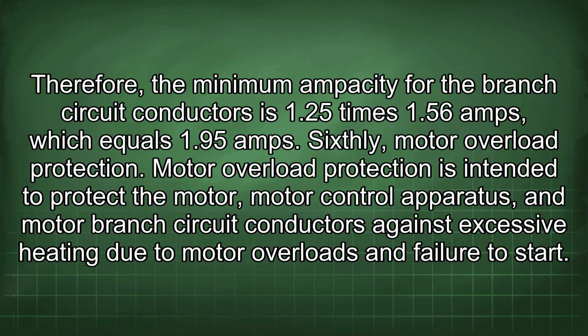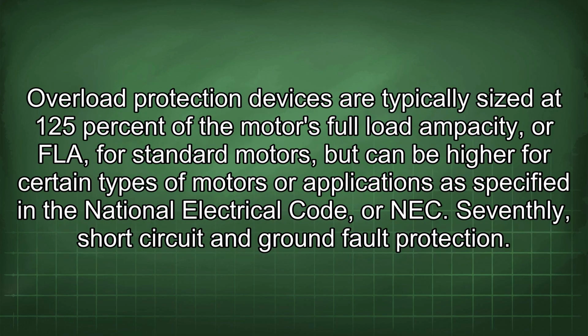Sixthly, motor overload protection. Motor overload protection is intended to protect the motor control apparatus and motor branch circuit conductors against excessive heating due to motor overloads and failure to start. Overload protection devices are typically sized at 125% of the motor's full load ampacity for standard motors, but can be higher for certain types of motors or applications as specified in the NEC.